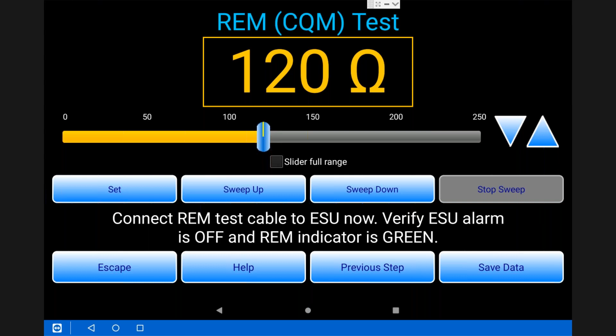So after returning, I can check to the next step. And as indicated for REM, we're producing resistance values. So the resistance is now set automatically at 120 because of the way the procedure has been created. Now the end user can connect the REM test cable because the resistance is there, and the appropriate indication we're looking for is that the green light should turn on and the alarm is not in an on state but is off. So we're going to say that the unit indicates that. So I hit save data. I'm going to indicate that the alarm is off, and as you can see, the result automatically equals a pass because of the way the PM procedure has been built. They don't have to have a manual or anything else with them. Everything they need is right here in the procedure.